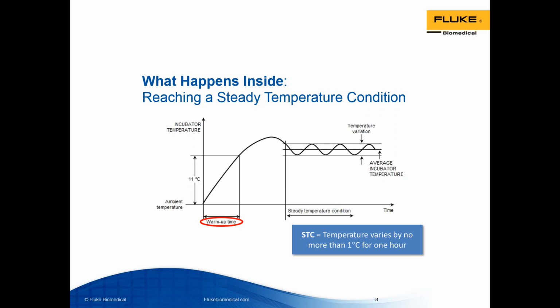An incubator's warm-up time is usually set in the manufacturer's manual, and this is very important to know, and we'll touch on this again a little bit later on, but the warm-up time must be measured to make sure that it's within about 20% of the time that's listed in the manufacturer's manual, and here's why. When a baby is being admitted to an incubator, the nurses or clinical staff will turn on the incubator and want to have it warmed up and ready for the infant to be placed inside. So if the manufacturer's manual states that it takes 25 minutes to warm up, the nurses, the staff, and the small infant that's going inside are going to expect that the incubator is going to be warmed up. So if the incubator isn't warmed up in this time, the consequences could be completely dangerous and even fatal to the newborn's health.